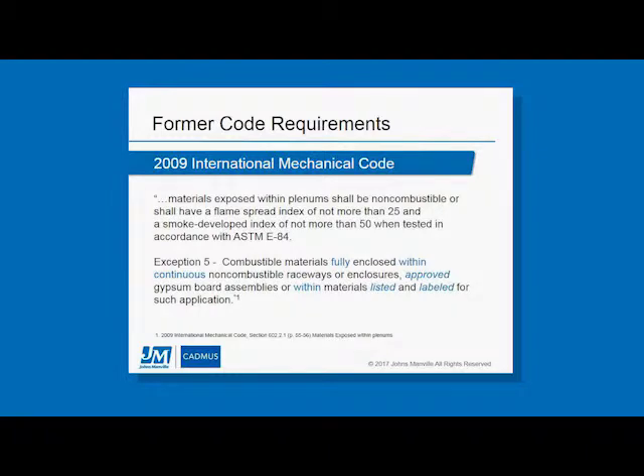As we move forward into 2009, the verbiage within that section of code changed. They still had the initial requirement of the 25/50 fire hazard classification rating, but now, dealing with combustible materials in a plenum space, the code had exception 5 that required those combustible materials, like piping, to be enclosed within non-combustible raceways or enclosures, or within materials listed and labeled for such application. And the words listed and labeled are emphasized in the code.